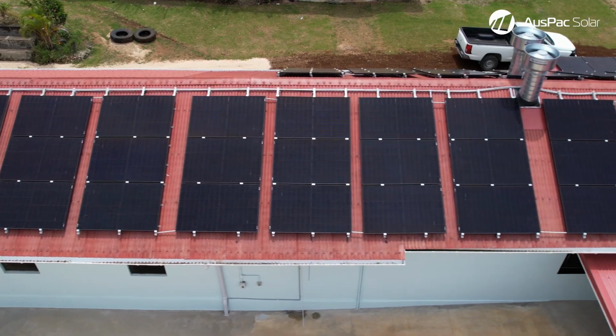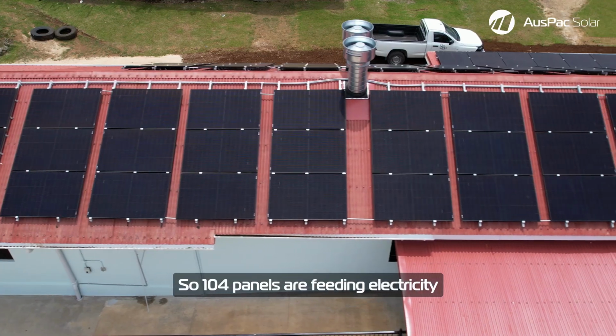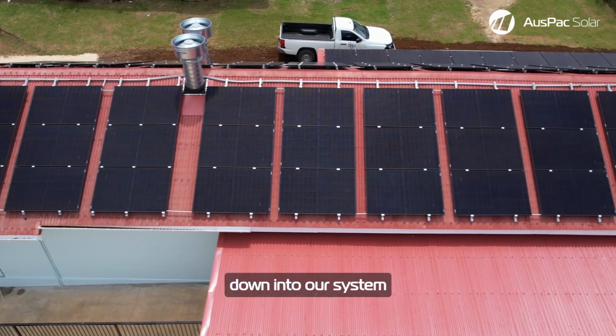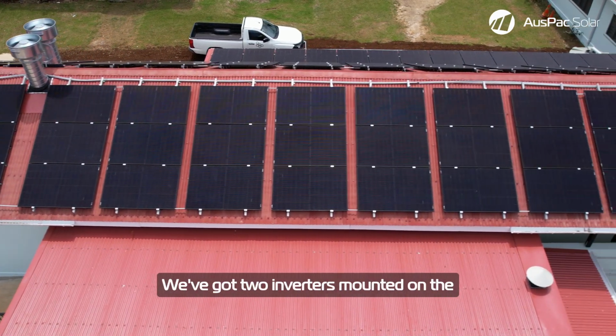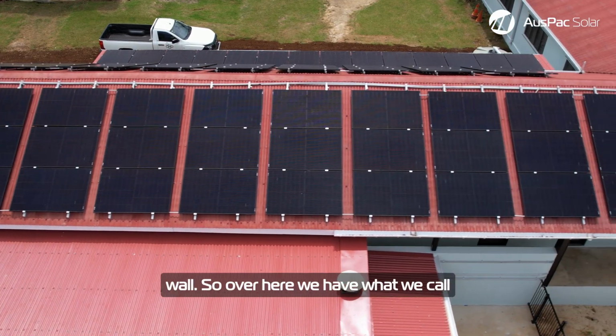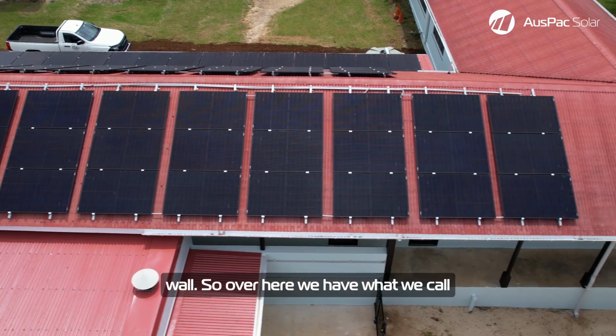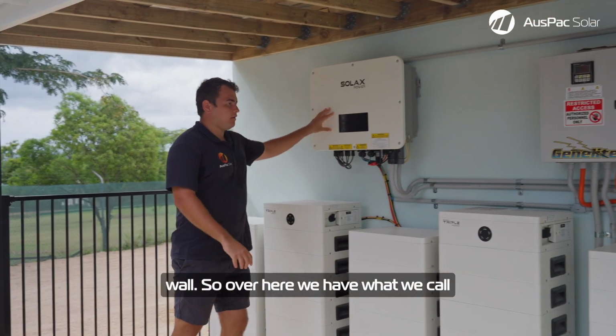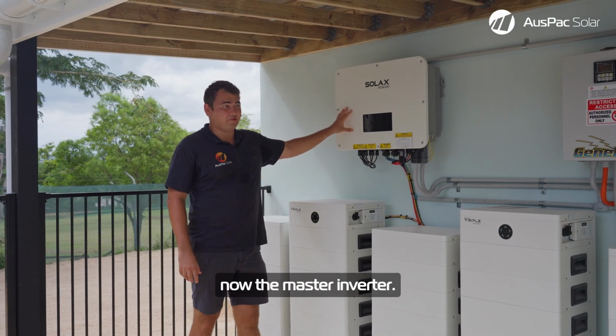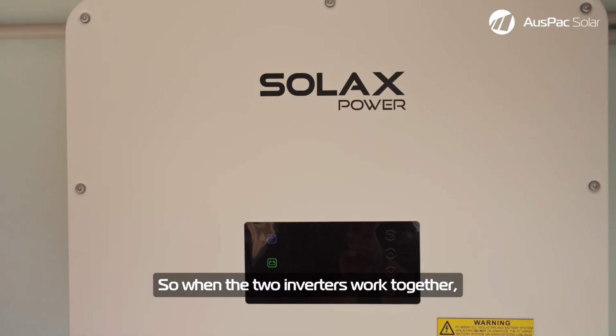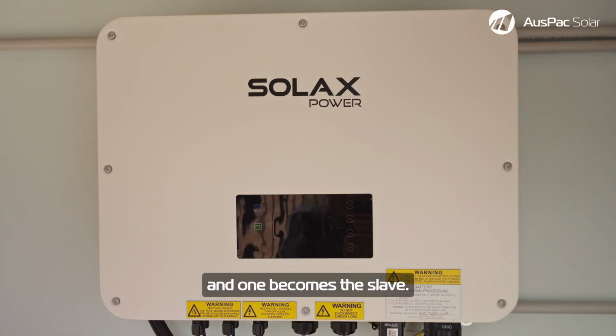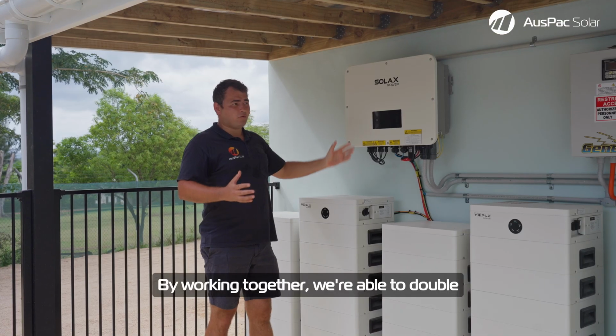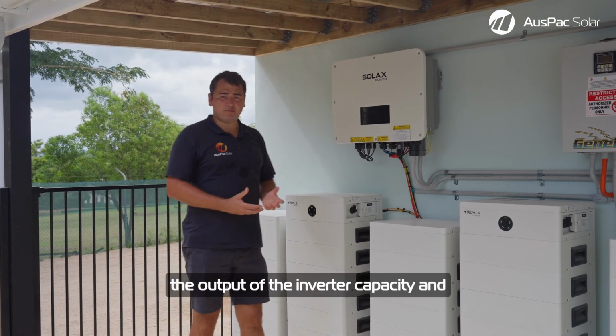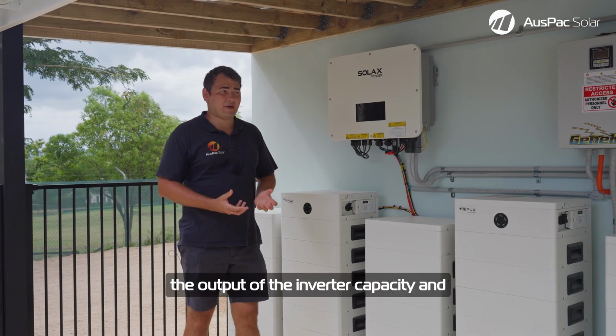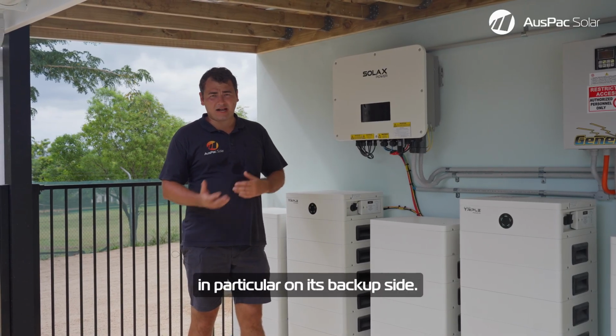So 104 panels are feeding electricity down into our system here. We've got 2 inverters mounted on the wall - this one is what we call the master inverter. When the 2 inverters work together, one becomes the master and one becomes the slave. By working together, we're able to double the output capacity of the inverters, particularly on the backup side.